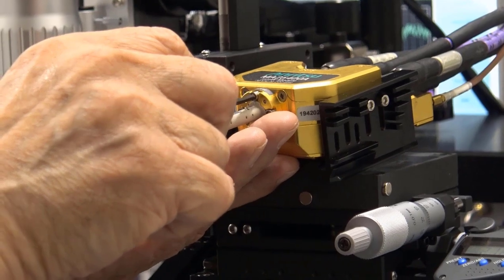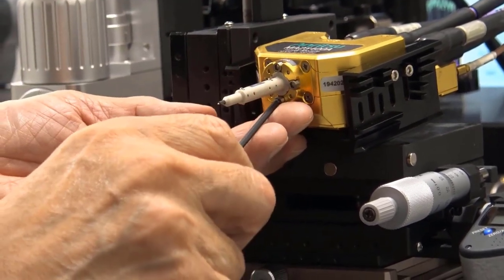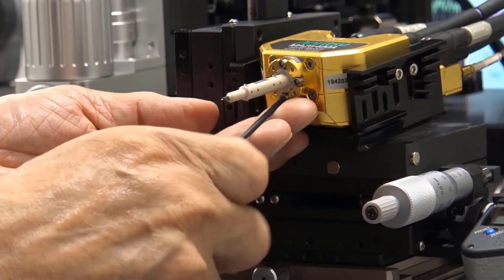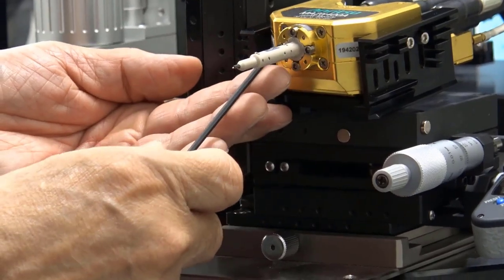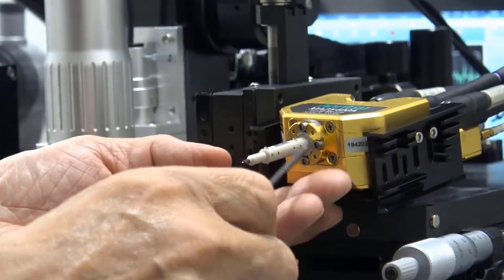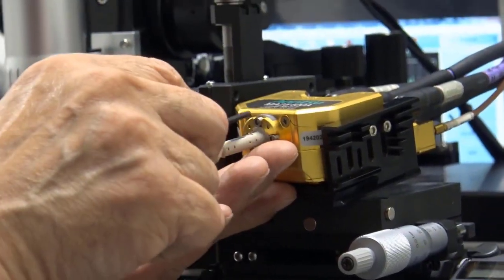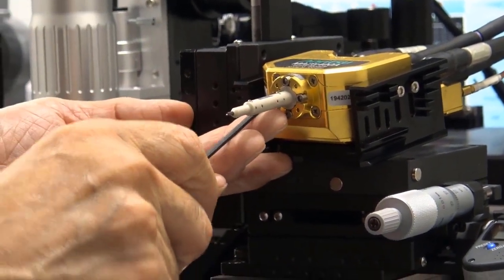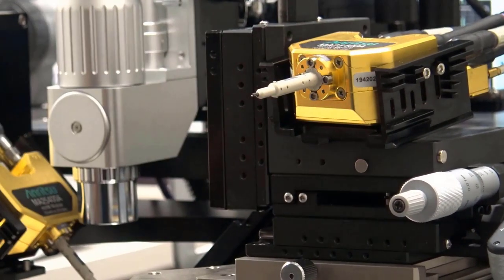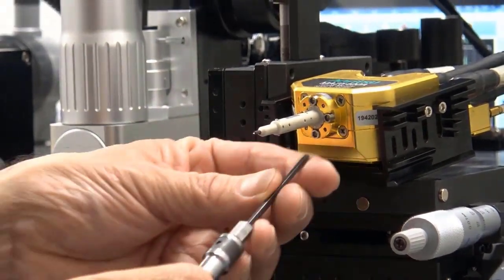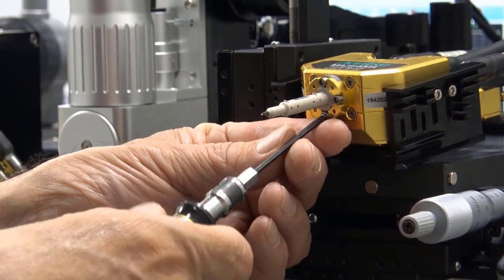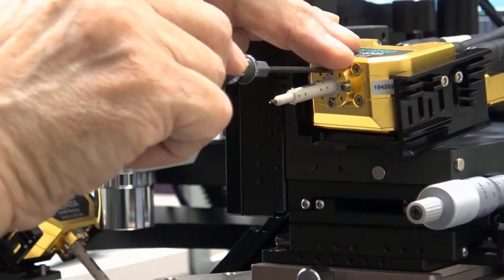And again, just work it a little at a time on all four sides so that you're sure that the flanges are completely mated with no gaps on the edge. And once we have it lightly tightened, then we can do our torquing. And the torque wrench is certainly a part of the accessory kit to help you with that.